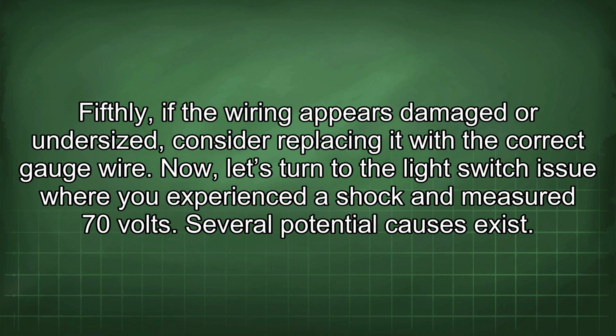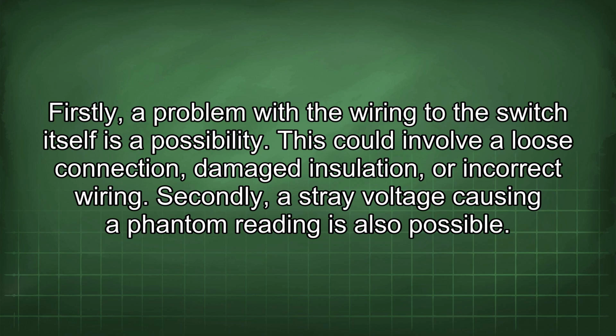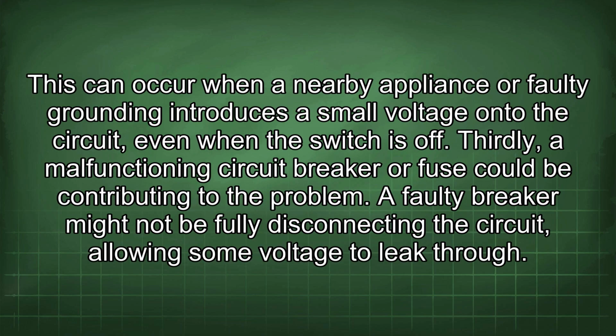Now let's turn to the light switch issue where you experienced a shock and measured 70 volts. Several potential causes exist. Firstly, a problem with the wiring to the switch itself is a possibility. This could involve a loose connection, damaged insulation, or incorrect wiring. Secondly, a stray voltage causing a phantom reading is also possible. This can occur when a nearby appliance or faulty grounding introduces a small voltage onto the circuit, even when the switch is off. Thirdly, a malfunctioning circuit breaker or fuse could be contributing to the problem.